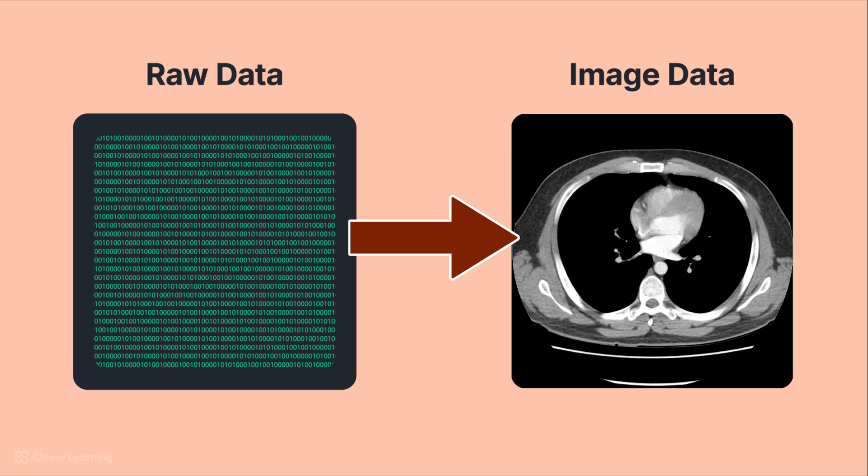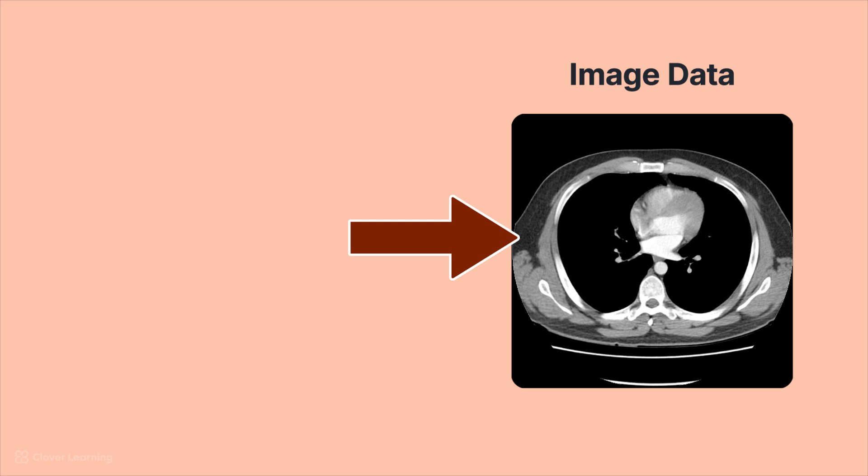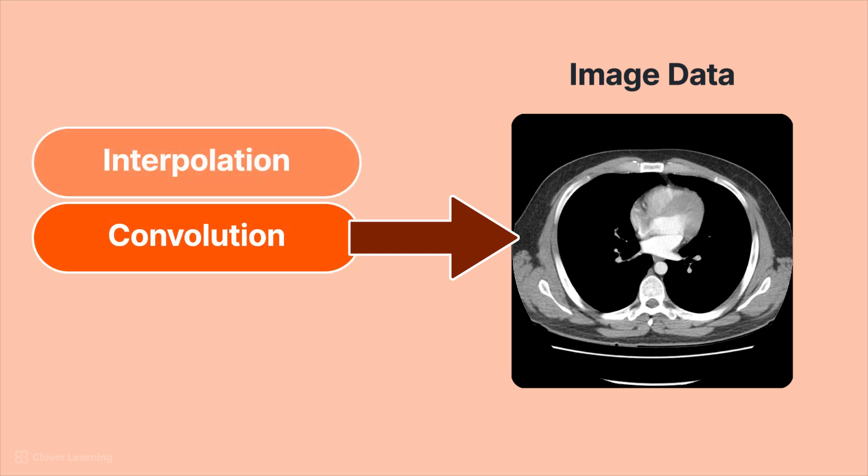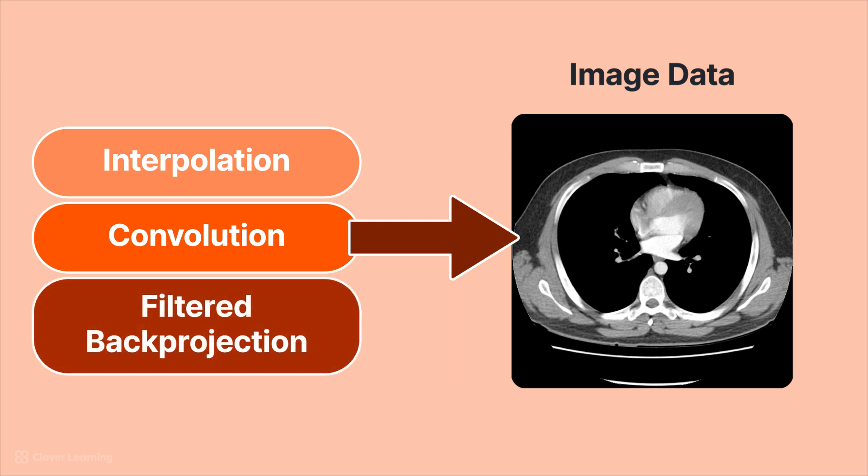So how does the reconstruction process actually work? There's actually three separate steps, all which contribute to reconstruction. The first step is interpolation, after that is convolution, and then finally, filtered back projection. Each of these processes are mathematical manipulations of the data acquired by the detectors. And without these manipulations, the CT image would just be a blurry mess of meaningless pixels.